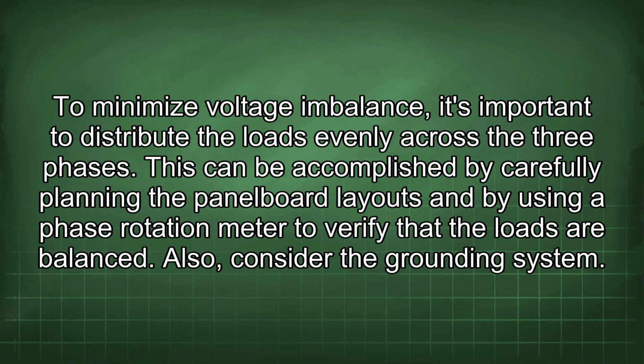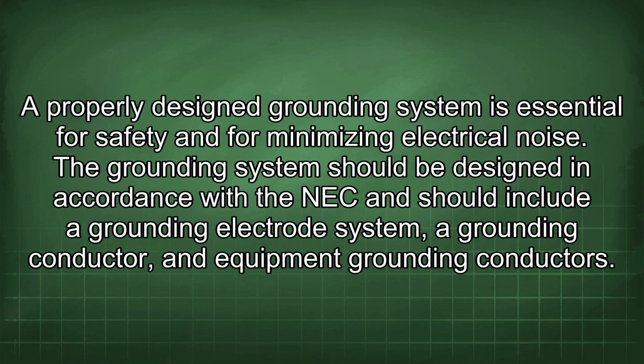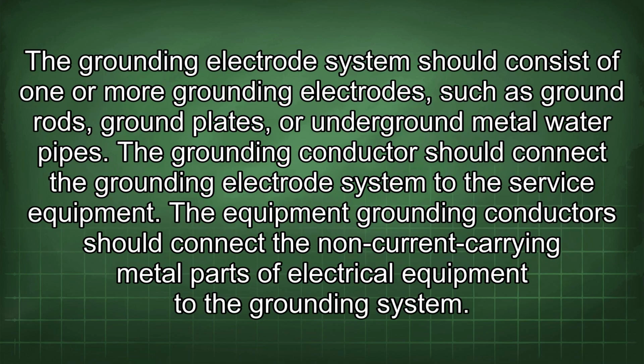Also, consider the grounding system. A properly designed grounding system is essential for safety and for minimizing electrical noise. The grounding system should be designed in accordance with the NEC and should include a grounding electrode system, a grounding conductor, and equipment grounding conductors. The grounding electrode system should consist of one or more grounding electrodes, such as ground rods, ground plates, or underground metal water pipes. The grounding conductor should connect the grounding electrode system to the service equipment. The equipment grounding conductor should connect the non-current carrying metal parts of electrical equipment to the grounding system.